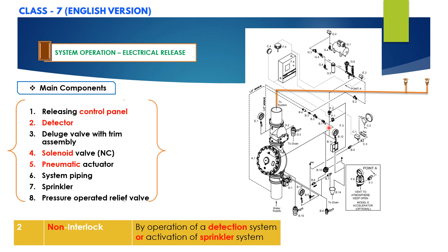The orifice allows water to flow slowly but will fill and pressurize the system. In the set condition, water supply pressure is trapped in the priming chamber of the deluge valve by the check valve, and both the normally closed solenoid valve and pneumatic actuator are held closed by pneumatic pressure maintained in the sprinkler piping. The pressure in the priming chamber holds the deluge valve clapper closed, keeping the outlet chamber and system piping dry.